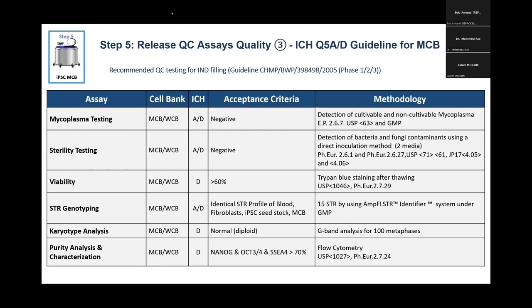Mycoplasma is a good example: PCR-based testing methods like mycoplasma light are cheap, reliable, and widely used, but are not recognized as validated assays by the FDA. You can still use them, but then you have to generate your own validation data to show equivalence to a validated test. Either use a validated test, or if using a non-validated test, validate it yourself and provide that data to the FDA. So look at the test required, check the guidances, and use a validated vendor.